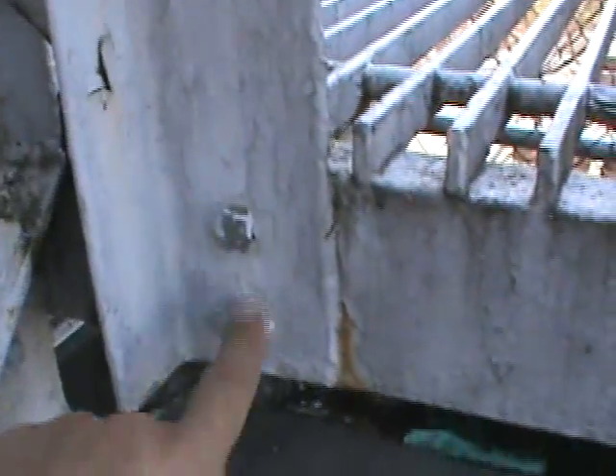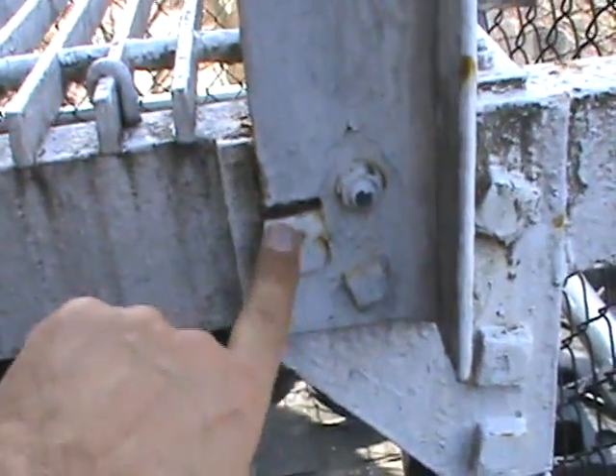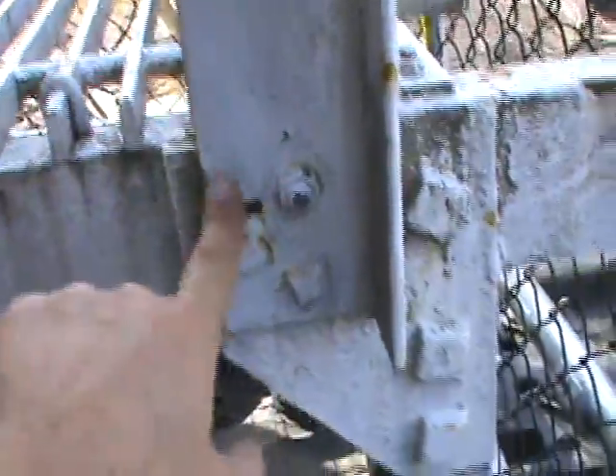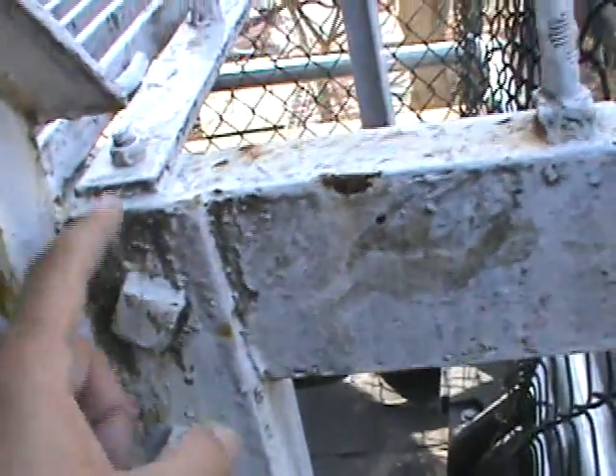This is what's called reinforcement. So somebody had the original, which is in good order, and they swapped out one. And sometimes that's one of the options. You know, here's another one. They kept the two originals, put in a bolt here to basically reinforce this section. That starts eliminating the load test. So it's things like this that we can do. If there's room for another bolt, sometimes we don't have to get rid of the original. We just back it up, and that allows us to eliminate the load test.